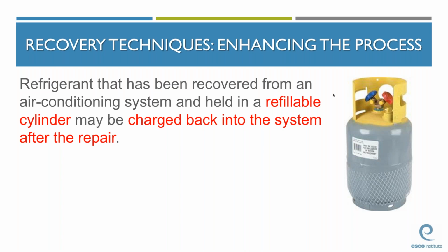Also, make certain that your students know that although recovered refrigerant can be reused, this is assuming that the recovered refrigerant was stored in a recovery cylinder that was properly evacuated prior to the recovery process. Once again, if the recovery tank was not properly evacuated, there's a good chance that the recovered refrigerant is now contaminated.